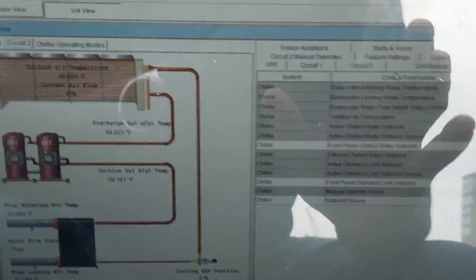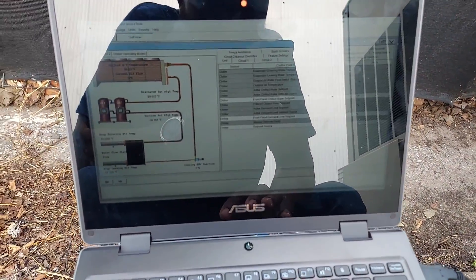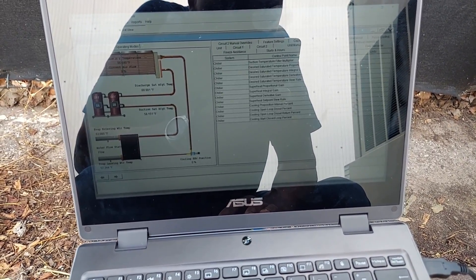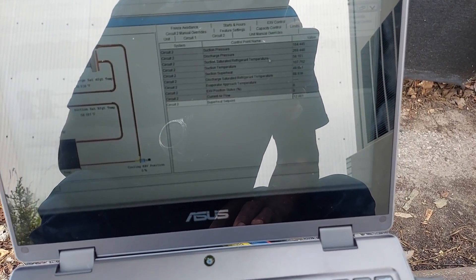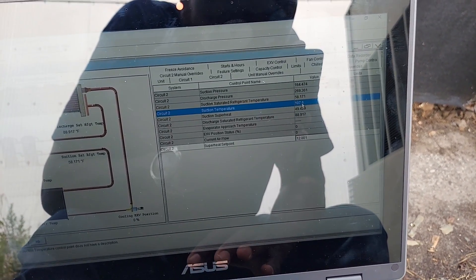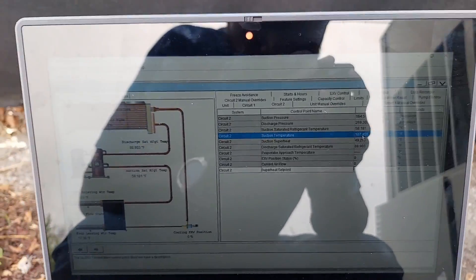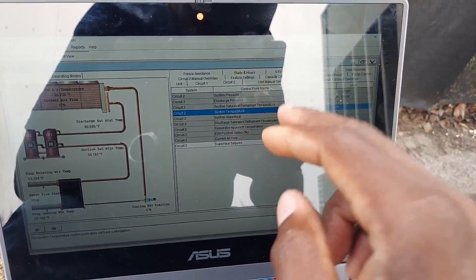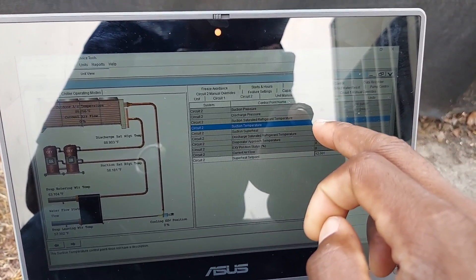I don't see that particular sensor here, but this is mainly what this video was about — showing you how to get in. Now looking at circuit number two, the suction temperature is reading 107°F — that's no good. There's no way that pipe is that hot. The chilled water temperature is in the 50s. I'm going to go back there right now and check it with my thermometer.